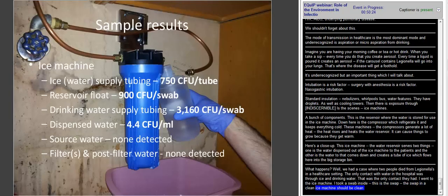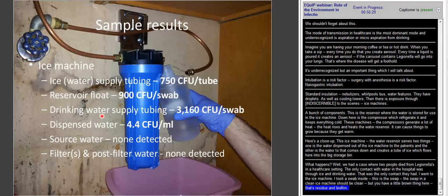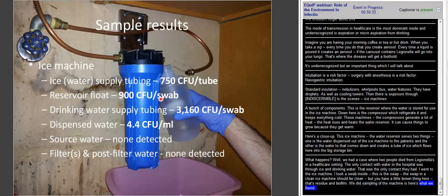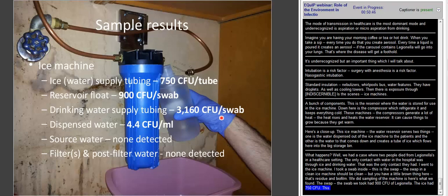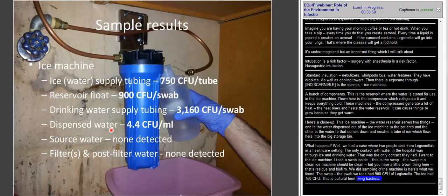So we did a bunch of sampling of the machine, and here's what we found: the swab from the reservoir had 900 CFUs of Legionella. The ice had 750 CFUs—this is culturable living Legionella bacteria. The drinking water supply tube had almost 3,200 CFUs in the swab. The dispensed water had 4.4 CFUs.